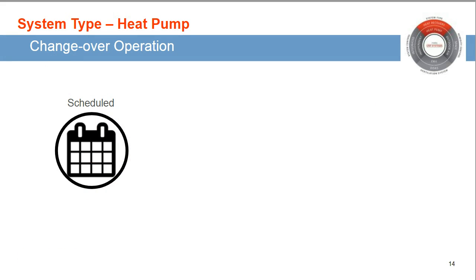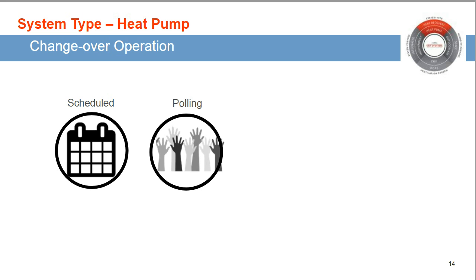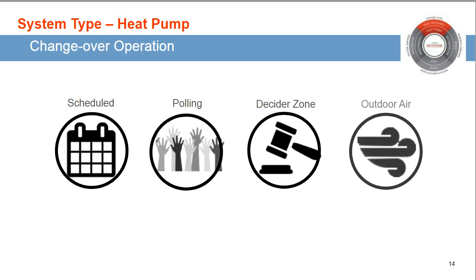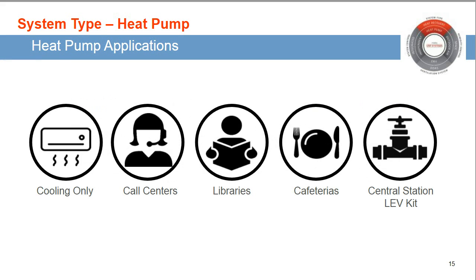So when it comes to heat pump systems, there are several changeover algorithms available as part of a heat pump VRF system control network. From a practical standpoint, no changeover algorithm is without its potential comfort compromise. Examples of algorithms used for changeover methods include using a schedule, polling zones, establishing a decider zone, or using outdoor air temperature. This leads designers to limit heat pump systems to cooling-only applications or applications with a common demand for heating or cooling in all zones. Examples for this might be a call center with a large open office area, a library interior, or even a school area like a cafeteria.